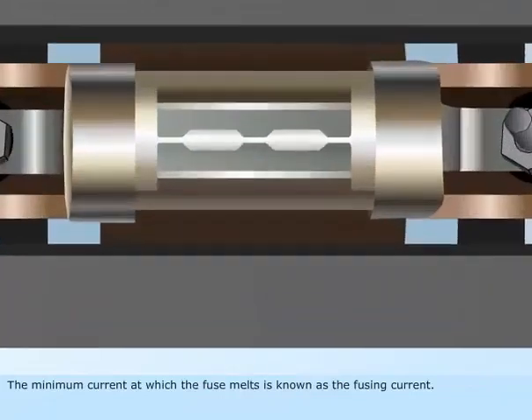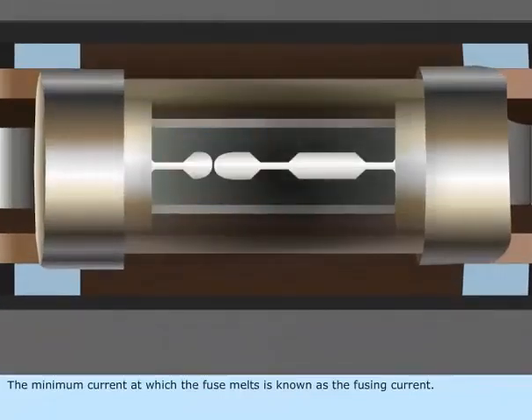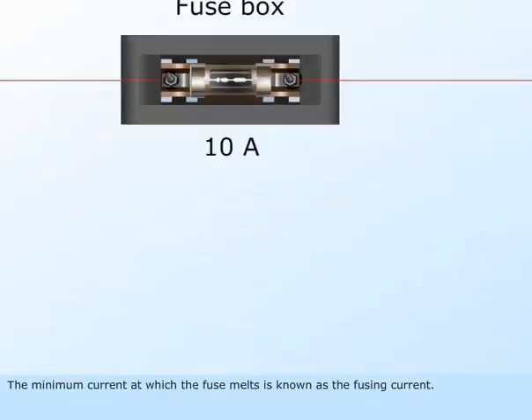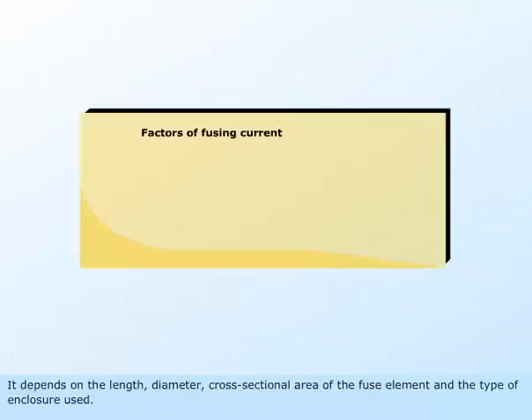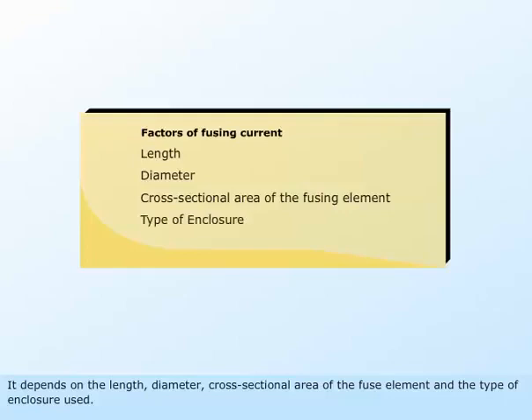The minimum current at which the fuse melts is known as the fusing current. It depends on the length, diameter, cross-sectional area of the fuse element and the type of enclosure used.